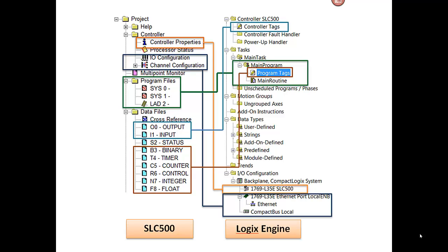And then within that instance of that instruction, you declare what part of that data structure in system variables you want to look at. If you want to change a value in the system variables, you have to use an SSV, set system variable. So you've got a get system variable and a set system variable.